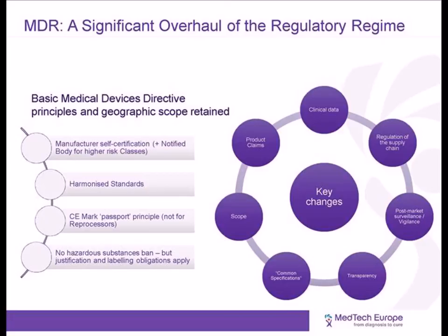Now, on the right hand of the slide, some key changes. The most obvious change in the EU MDR is the increased requirements for the safety and performance of devices to be documented. It is essential to understand that no grandfathering is foreseen under the MDR. So all devices destined for future EU sales will need to comply with the new rules.